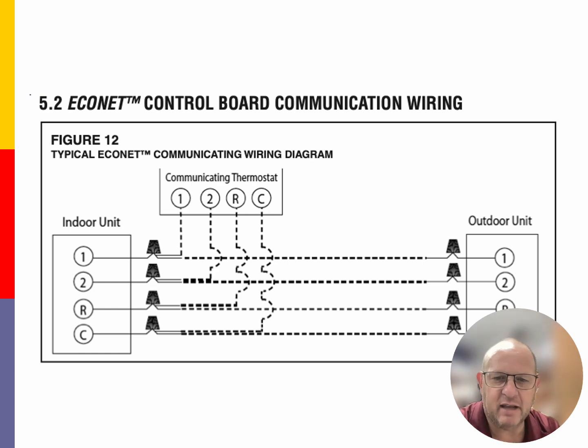With communicating systems, there's a lot of things that we can do to look at different aspects of the system: airflow, capacity, subcooling, superheat, discharge pressure, suction pressure. All of these things are going to be built into these units because they're very sophisticated. I like to look at communicating systems as well as gas modulating systems as units that have a gas pedal on them.